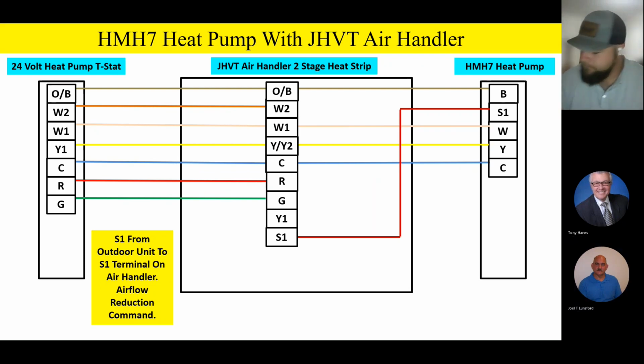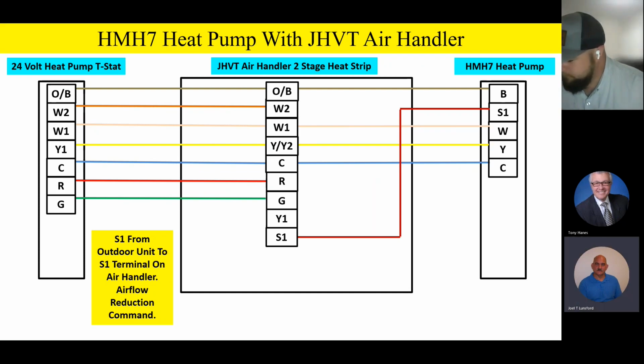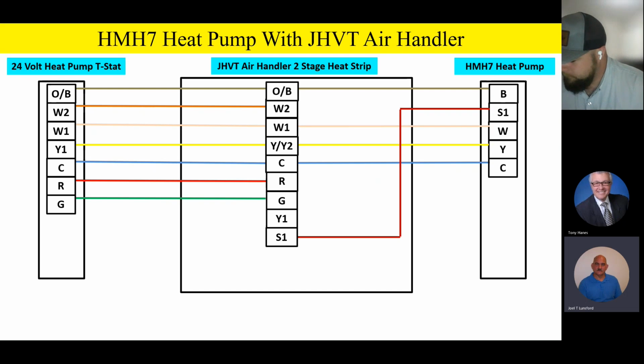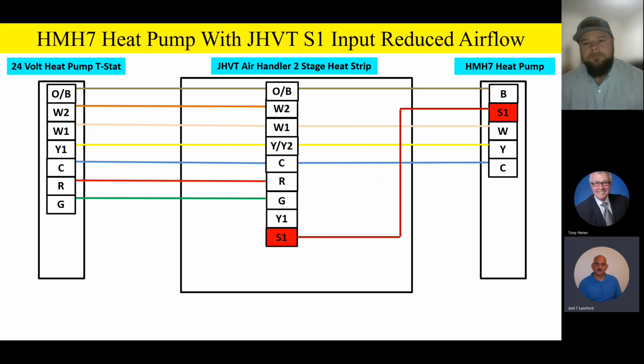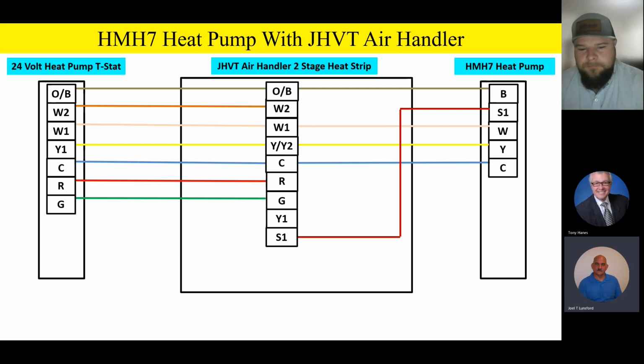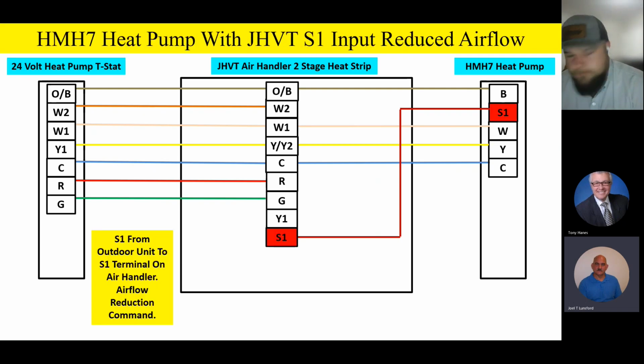Okay. Well, fantastic. Let's go ahead and take a look then, just a little animation. Let me back up one more time. So whenever the outdoor unit is calling for reduced airflow, it's going to energize that S1. You'll see that animation there. It energizes the S1 and it calls for airflow reduction directly onto the air handler itself. That's pretty cool the way that works.